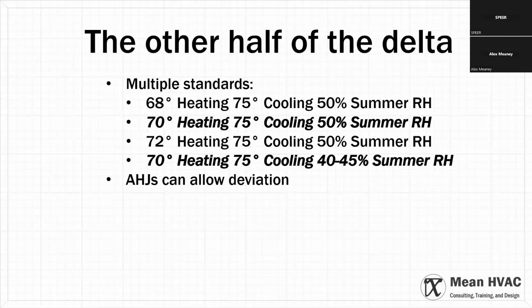It reduces the capacity. And so a procedure in a document associated with the Manual S, I don't know if it's normative or not, but I certainly would strongly recommend that people follow it, would be in very dry climates to adjust your relative humidity so that you are near zero on your latent load from your outside air to predict the indoor relative humidity for the performance of your air conditioner. So that's the one variation on 70, 75 that you might see that I would green light if I were you, because it's an appropriate design criteria in very dry climates.